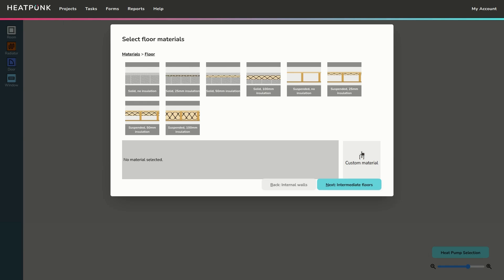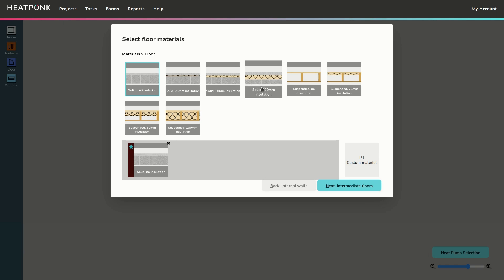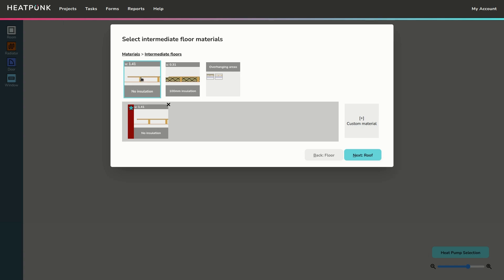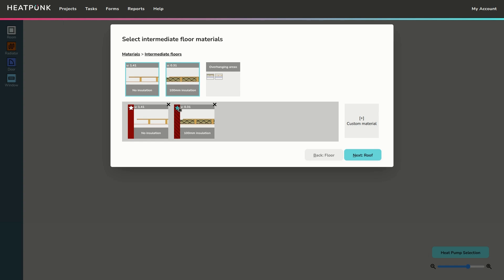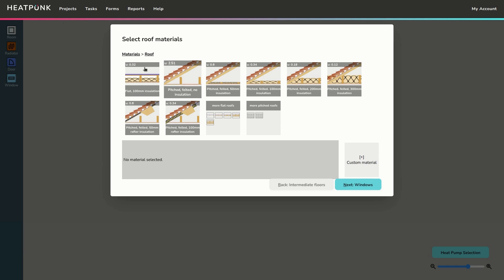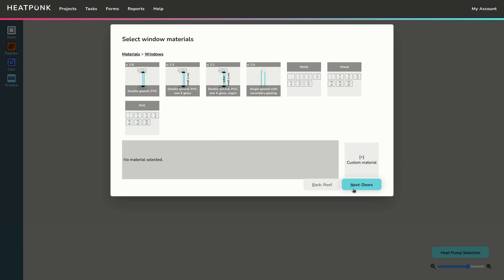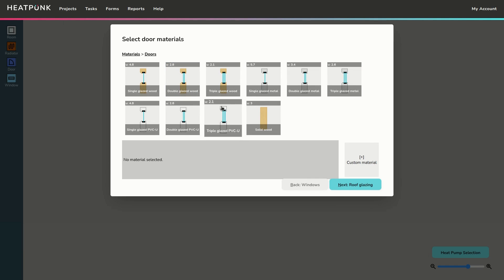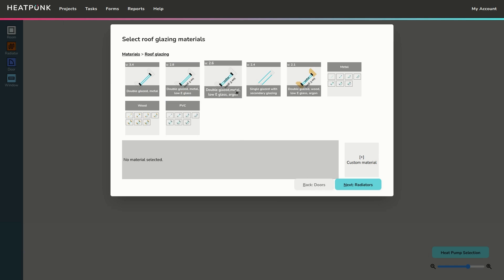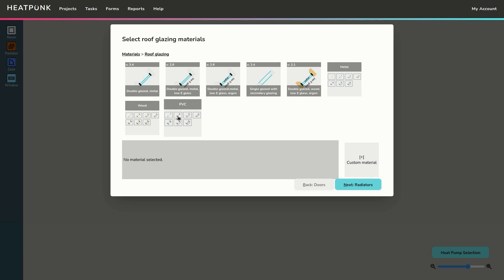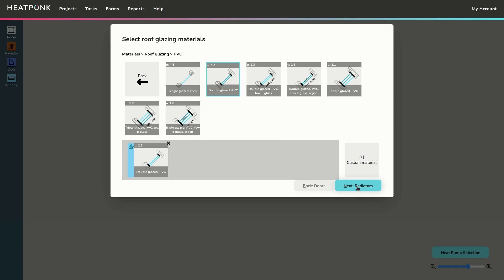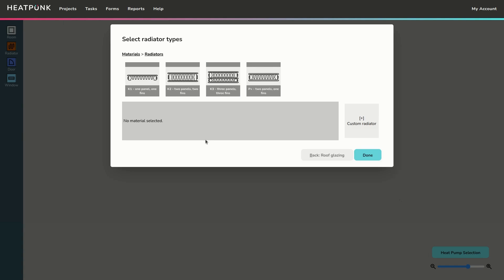There is a custom material button if you're unable to find what you need — you can enter U-values or use the tool to build up the layers. There are also internal wall sections, floor types (solid, insulated, or suspended), and roof types to select. When selecting materials, the first one gets a blue star indicating it's the default — it will be automatically used when building, but you can change it. Windows and roof glazing are also selected here; if you have Velux windows a material is required, but if you have no roof glazing it won't appear in the report — it just sits in your material library.